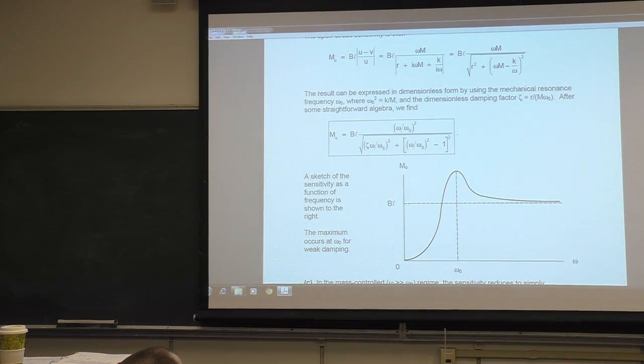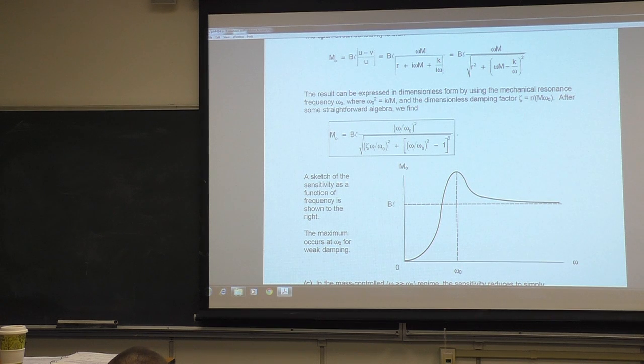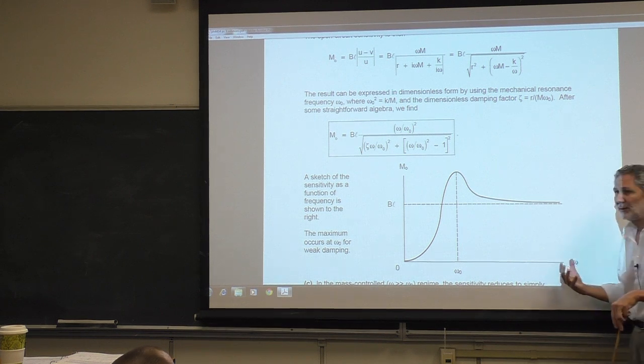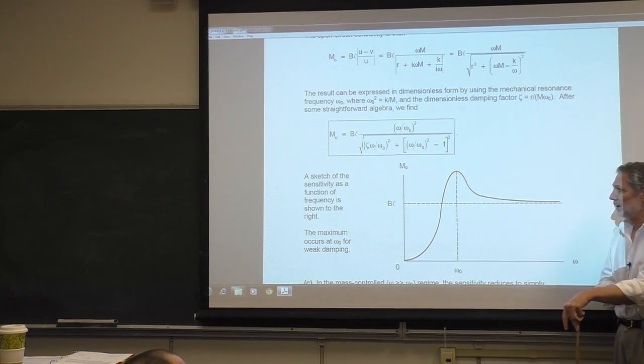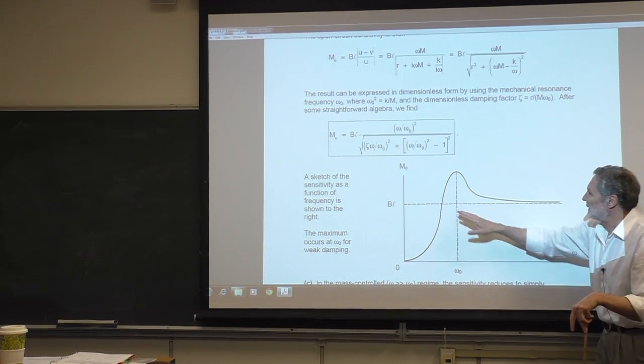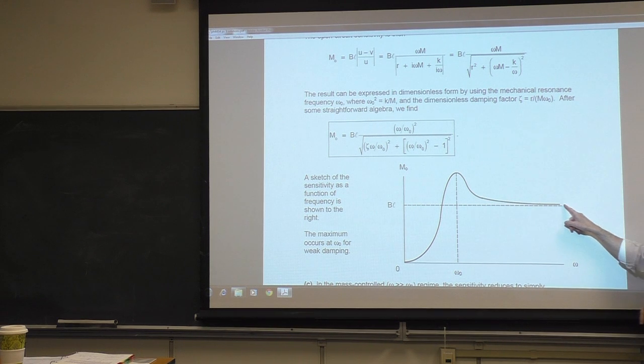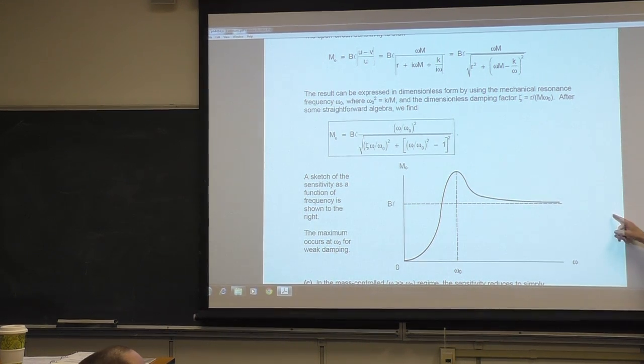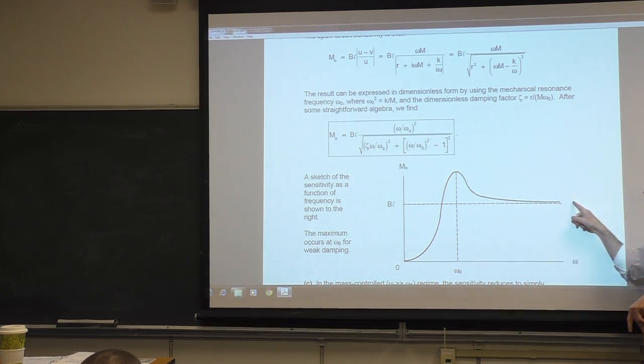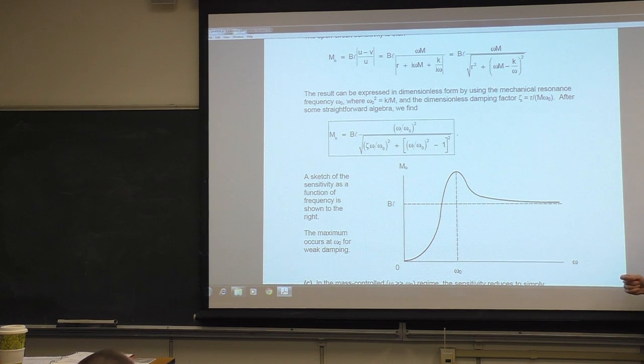Now, I don't mention it in here, but I need to tell you one of the reasons transducers aren't usually cheap, particularly measurement transducers, accurate measurement transducers, is they've gone a long way to make this device useful. So, before I talk about that, I need to say something here. You can see here that out in this region, as long as you're sufficiently far from the resonant frequency, you have a flat transducer. But I want to point out that it's flat because we chose velocity. The sensitivity here corresponds to the velocity. It's the volts per meter per second, right?